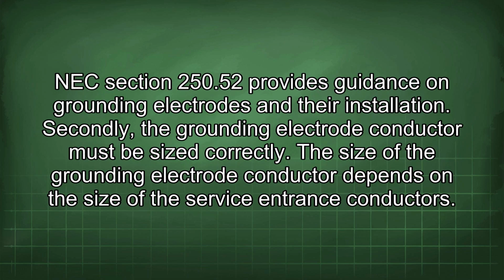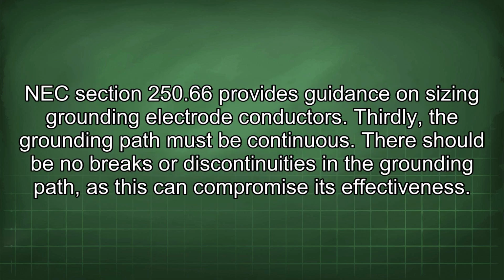NEC Section 250.52 provides guidance on grounding electrodes and their installation. Secondly, the grounding electrode conductor must be sized correctly. The size of the grounding electrode conductor depends on the size of the service entrance conductors. NEC Section 250.66 provides guidance on sizing grounding electrode conductors.